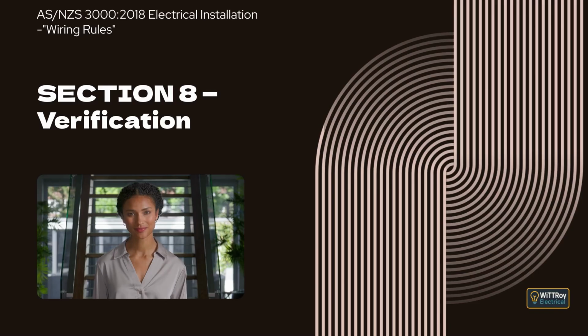Clause 8.3.3, Mandatory Tests. This clause explains that certain tests are mandatory and must be carried out on parts of electrical installations designed to operate at low voltage. These tests include continuity of the earthing system, insulation resistance, polarity, correct circuit connections, verification of impedance required for automatic disconnection of supply, and operation of RCDs.